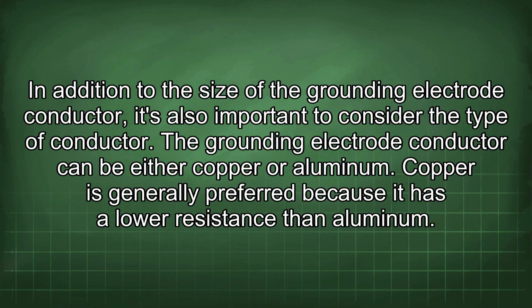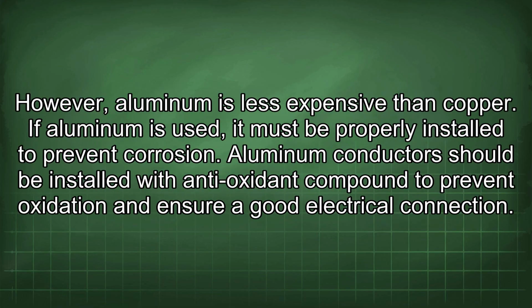In addition to the size of the grounding electrode conductor, it's also important to consider the type of conductor. The grounding electrode conductor can be either copper or aluminum. Copper is generally preferred because it has a lower resistance than aluminum. However, aluminum is less expensive than copper. If aluminum is used, it must be properly installed to prevent corrosion. Aluminum conductors should be installed with antioxidant compound to prevent oxidation and ensure a good electrical connection.